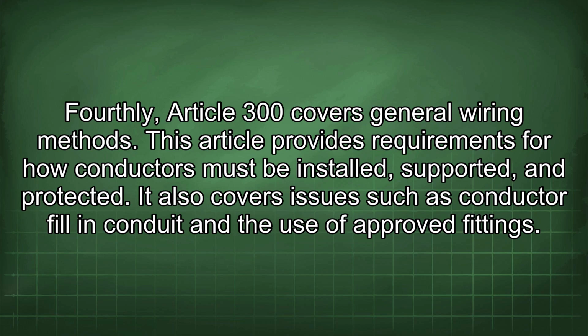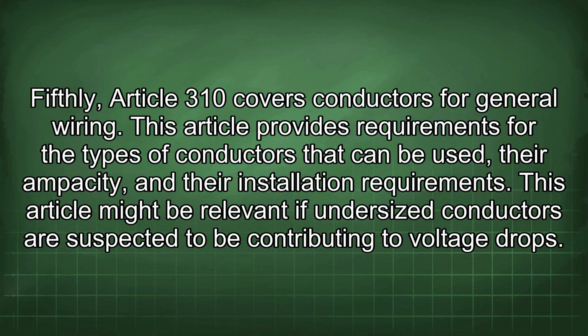Fourthly, Article 300 covers general wiring methods. This article provides requirements for how conductors must be installed, supported, and protected. It also covers issues such as conductor fill in conduit and the use of approved fittings. Fifthly, Article 310 covers conductors for general wiring. This article provides requirements for the types of conductors that can be used, their ampacity, and their installation requirements. This article might be relevant if undersized conductors are suspected to be contributing to voltage drops.